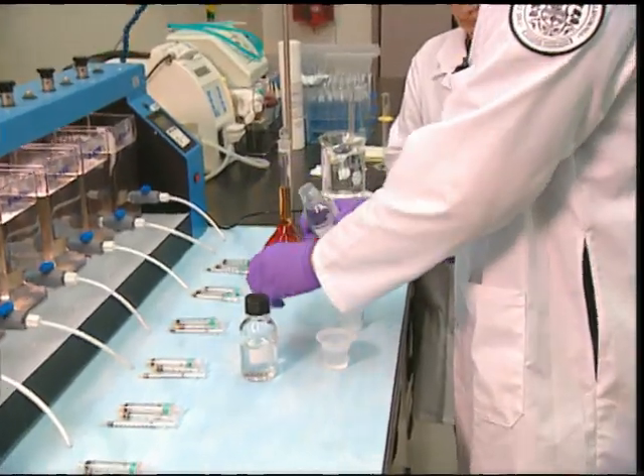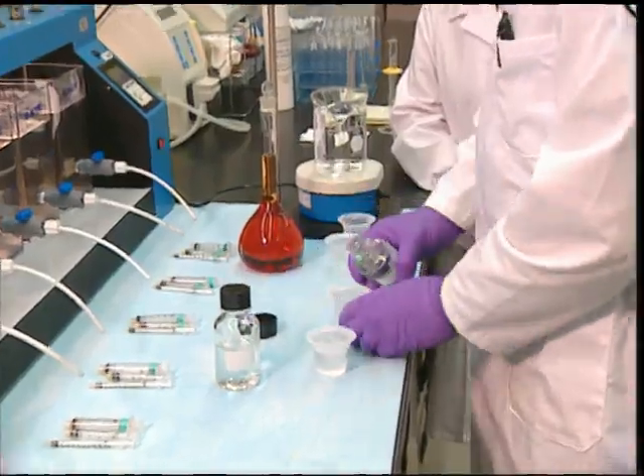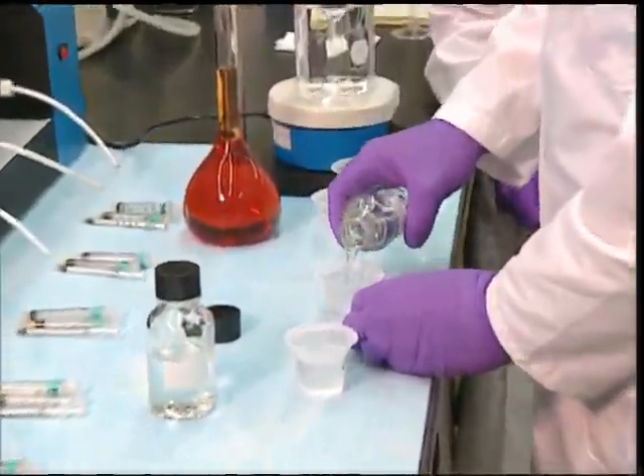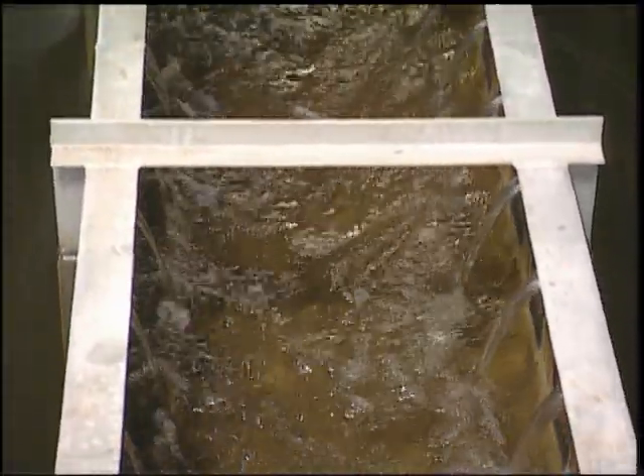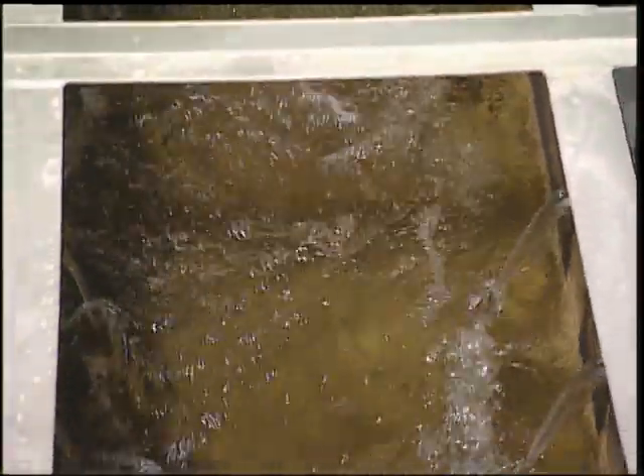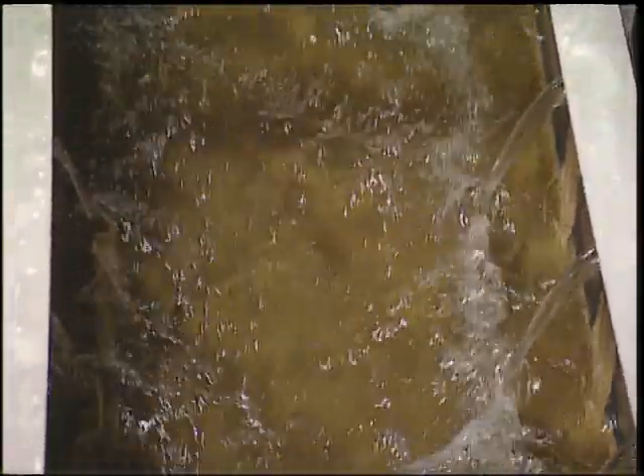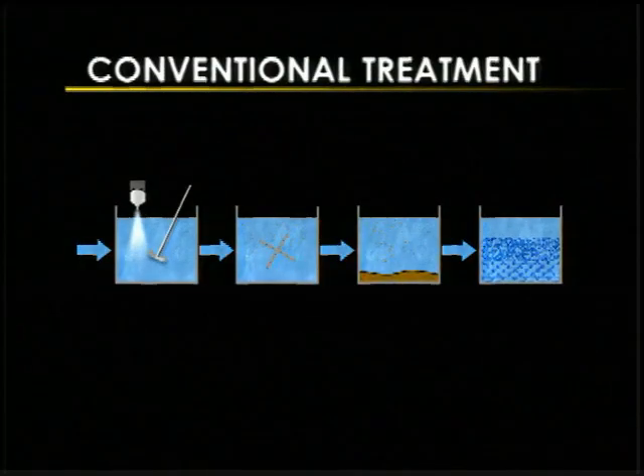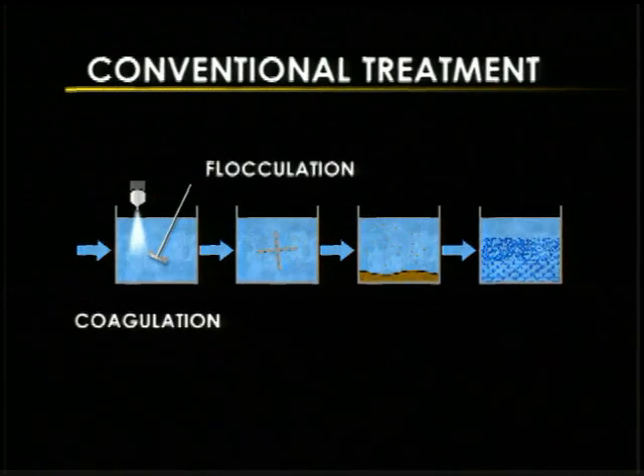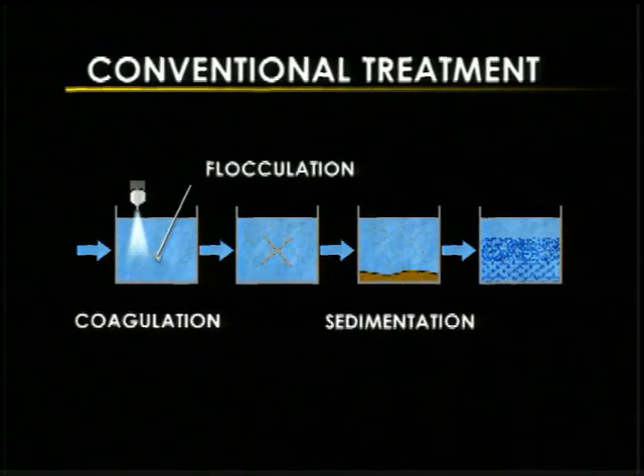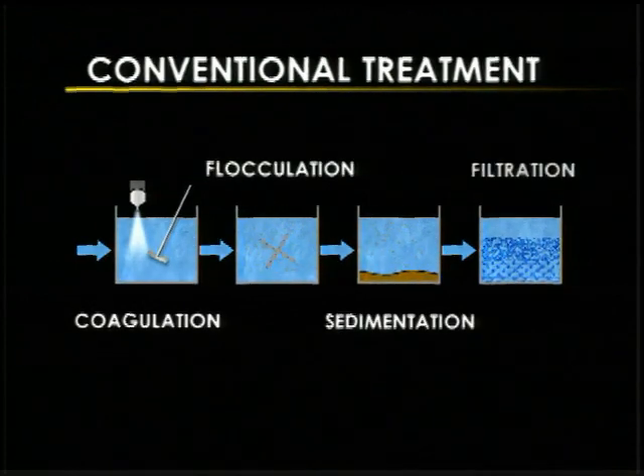The most common use of jar testing is to determine the appropriate use and dose of chemicals in water treatment. One objective of water treatment is clarification, the removal of particulate matter in the water. Particles are removed both chemically through coagulation, flocculation, and sedimentation, and physically through filtration.